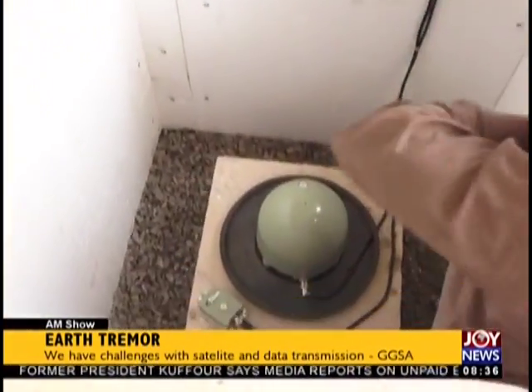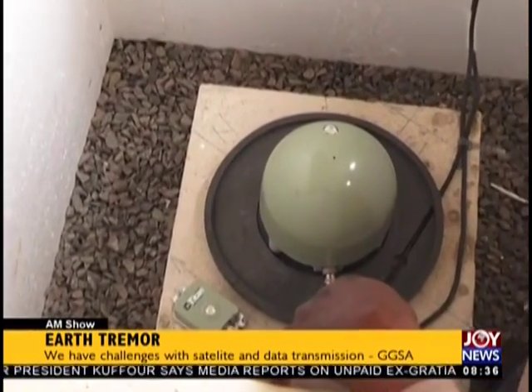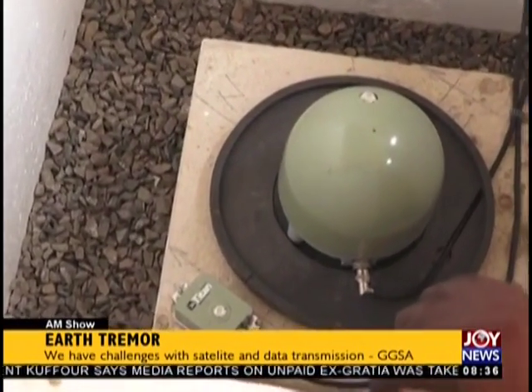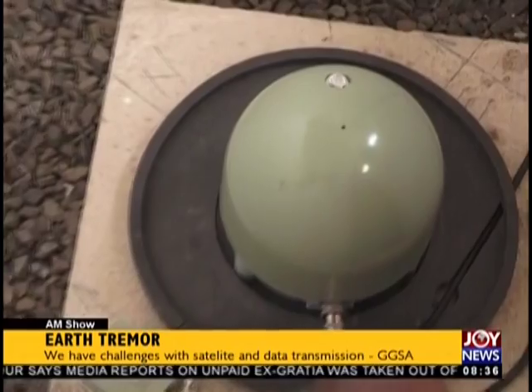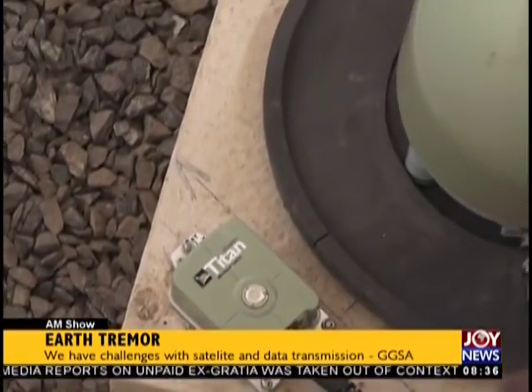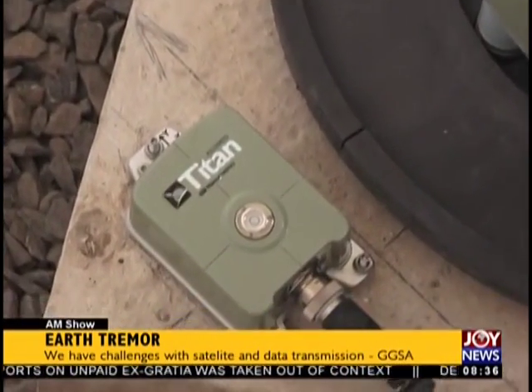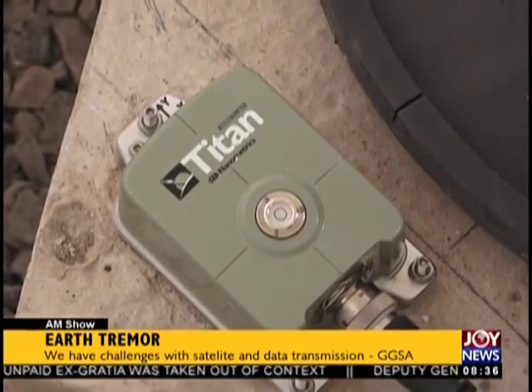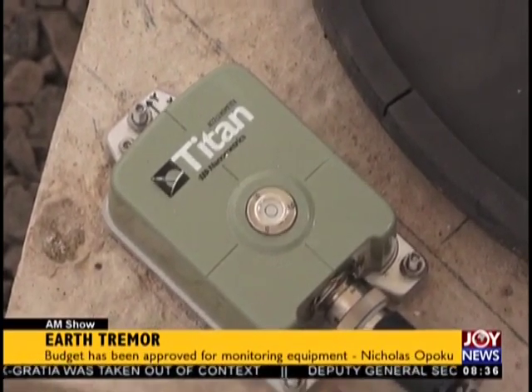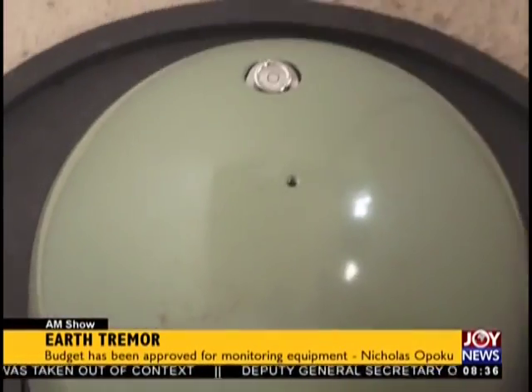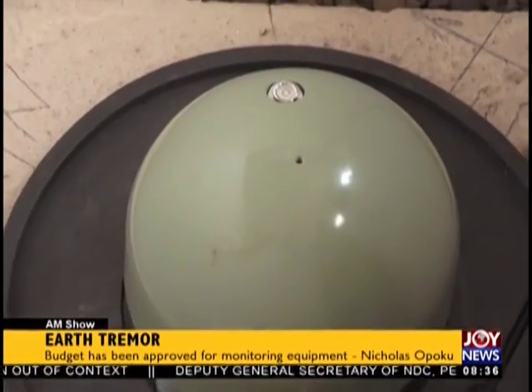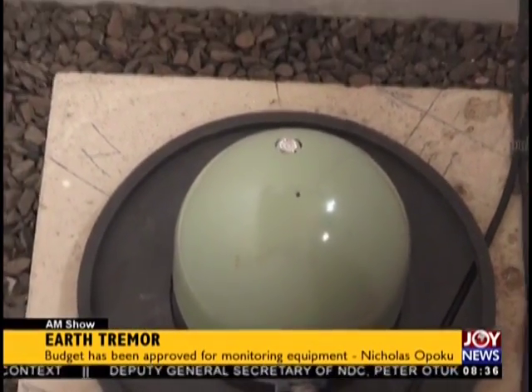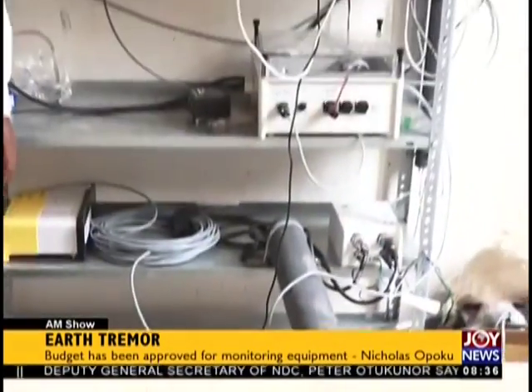So if I should mention again, this is a seismometer. This is a broadband seismometer. It is measuring ground velocities of the waves. The small one is a strong motion. It's not sensitive, so that one we don't cover it. The broadband seismometer is very sensitive, so we have to cover it and isolate it from the effect of wind. This is not sensitive, so the wind doesn't affect it at all. And that one is measuring ground acceleration.